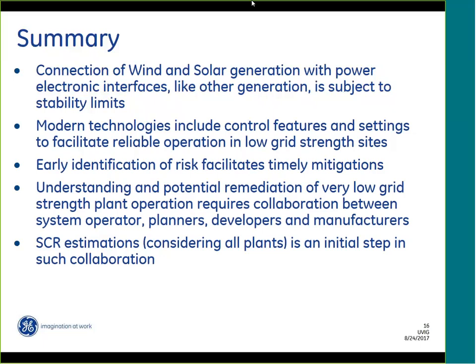So a short circuit ratio of 3 or more is reasonable or high. In the solar industry, maybe 5 or more is high. The value of 3 is borderline in some cases. Ratios between 3 and 1.5 are challenging, and there it depends on the technology, since the response depends so much on the controls. Let's say 3 to 1.5 is the range where things may be okay or not depending on the technology. Between 1.5 and 1 is really hard, and that may or may not work.